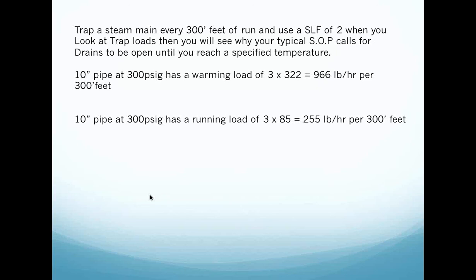to go home safely. But let's just say that we had this 10-inch pipe at 300 psig, has a warming load of 322 pounds per hour, and remember, that's per 100 feet. So if we place a drip trap every 300 feet, it's going to be 3 times the 322 pounds per hour, so it'll be 966 pounds per hour for that 300-foot section of that 10-inch, 300-pound steam main.